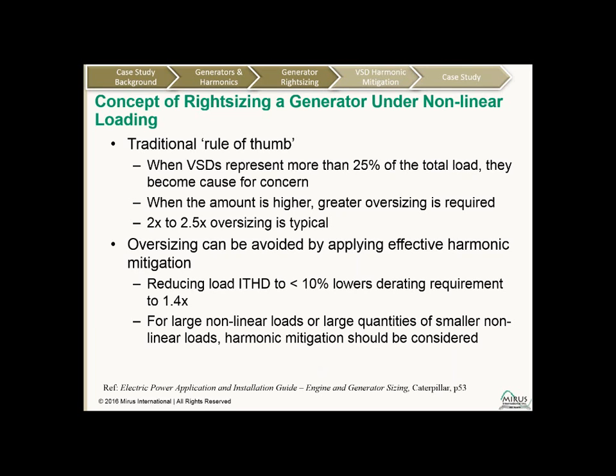If you reduce the current distortion to less than 10%, that lowers the derating requirement to 1.4 times. So for large nonlinear loads or large quantities of smaller nonlinear loads, harmonic mitigation should always be considered. If we can reduce it to even less than 10% THD, then obviously we can get closer and closer to a 1-to-1 sizing of generator to load.